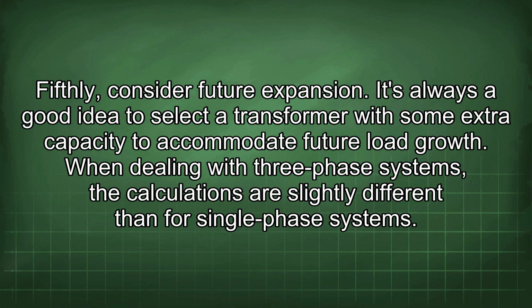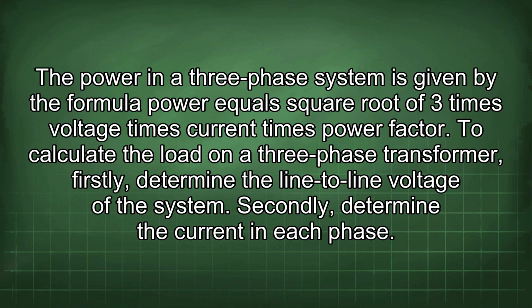load growth. When dealing with three-phase systems, the calculations are slightly different than for single-phase systems. The power in a three-phase system is given by the formula power equals square root of 3 times voltage times current times power factor. To calculate the load on a three-phase transformer, firstly, determine the line-to-line voltage of the system. Secondly, determine the current in each phase.